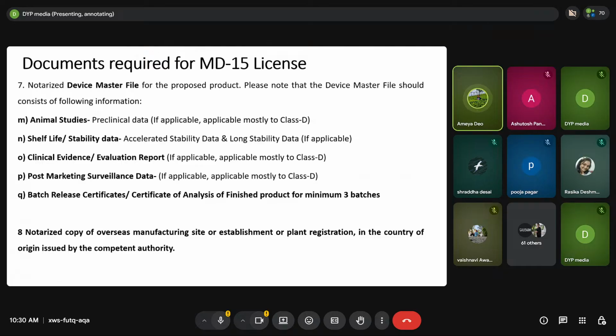Now, the most important thing here is that CDSCO might ask you about clinical trials in India as well. Sometimes, if it is a Class D device, an implant, or a device that will remain inside the body for more than 6 months, then CDSCO might ask you for the clinical data or the safety data from the Indian perspective. So for that, we need to assign a clinical organization who can handle that data. Then only CDSCO will provide the license. Also required is a manufacturing establishment plant registration in the country of origin, issued by the authority. Please go to the next slide.